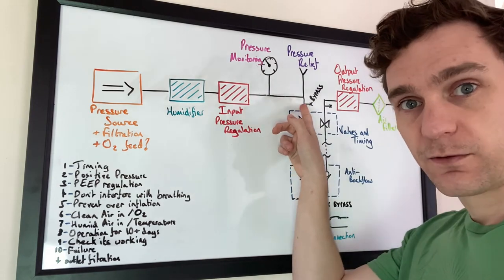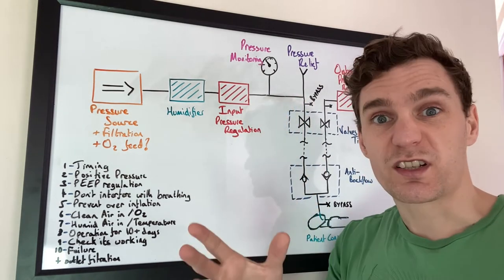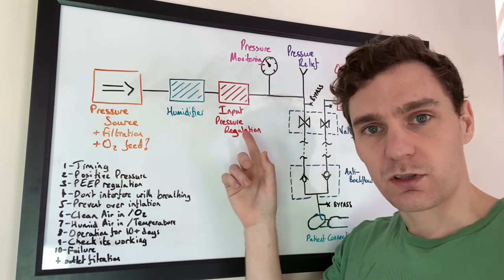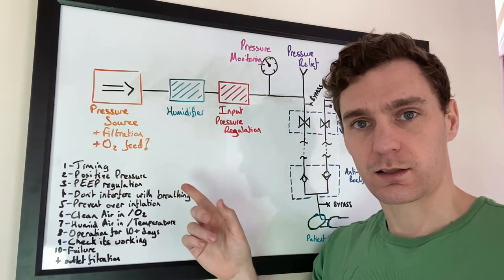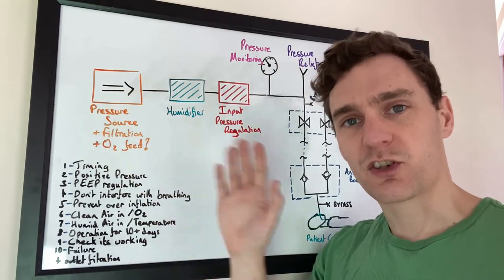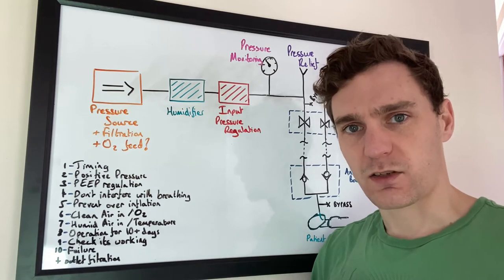Next thing is pressure relief. This could be a burst disc. This could be a water bottle. This is to make sure that you don't over pressure the patient's lungs. If something goes wrong with any of this system upstream, you don't end up applying too much pressure and damaging the patient's lungs.